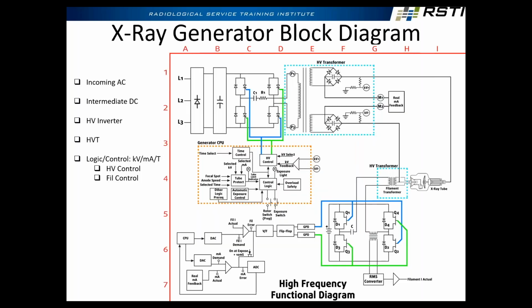Let's skip ahead to page 37. Probably hard to see here, kind of a small diagram. This is the fundamental concept for which every X-ray generator works. On the left-hand side I broke this down into the basic categories. Top left corner, what's happening? Incoming AC. So if it's three-phase, it'd be 480 volts, right? 480 three-phase from the customer's wall box, the power breaker coming into the room. What am I doing here? I'm filtering that and converting it to DC.